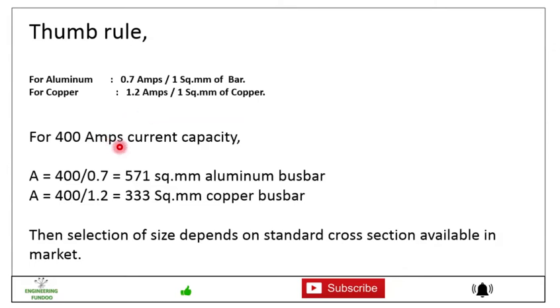So let's say for 400 amps current capacity, area required will be 400 divided by 0.7 for aluminum, that will be 571 square mm aluminum busbar. And for copper, 400 divided by 1.2, 333 square mm copper busbar. Friends, this area is not the standard one, so we have to take the next higher size.